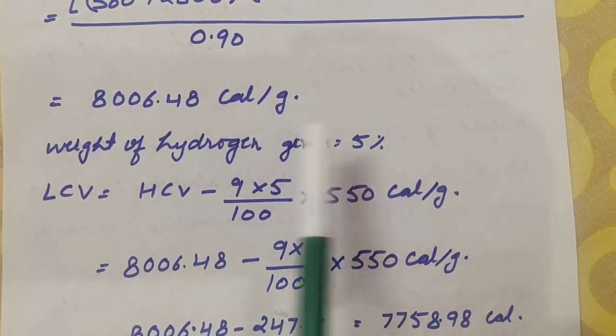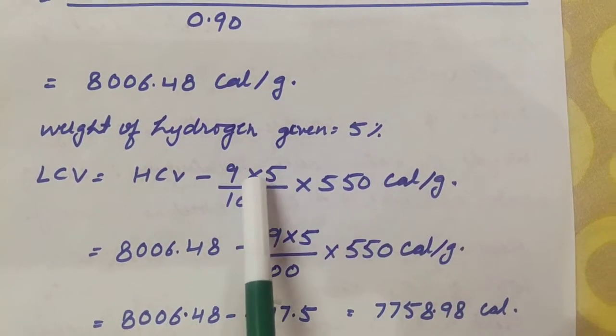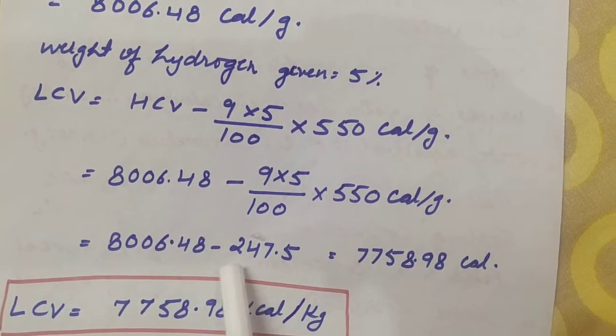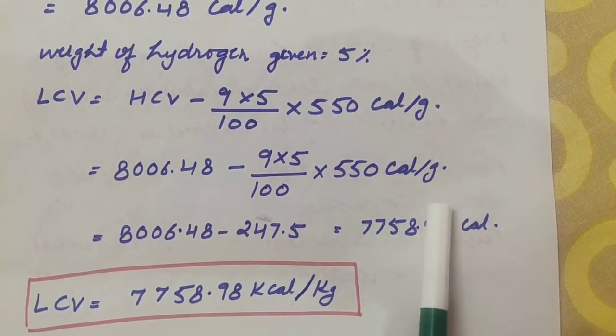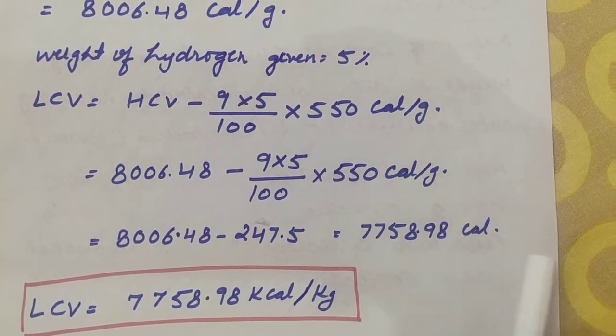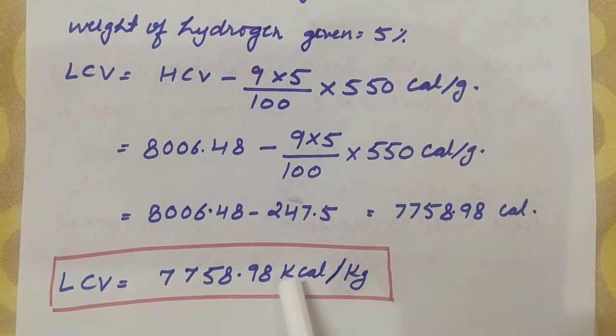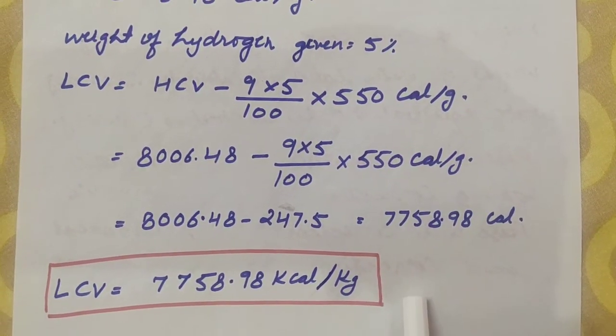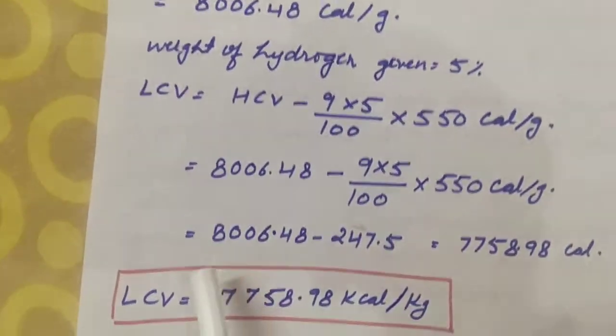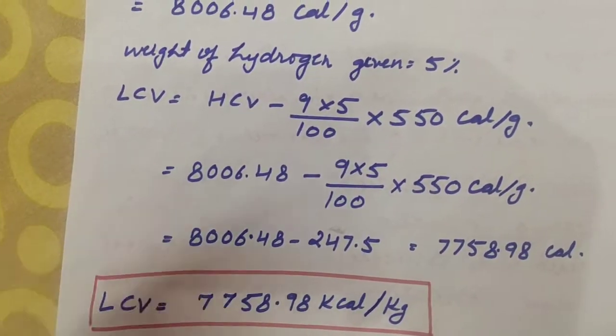The weight of hydrogen given is 5%. To calculate the lower calorific value, the formula is: LCV = HCV − 9 × (H% / 100) × 550. Substituting: 0.09 × (5/100) gives 247.5 calories per gram. Subtracting this from the HCV, we get the lower calorific value. Converting to kilocalories per kilogram, the answer is 7758.98 kilocalorie per kilogram.